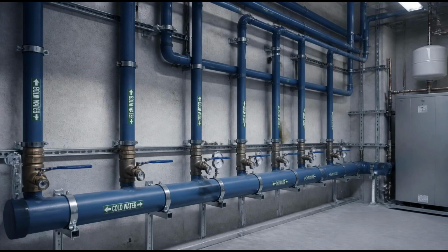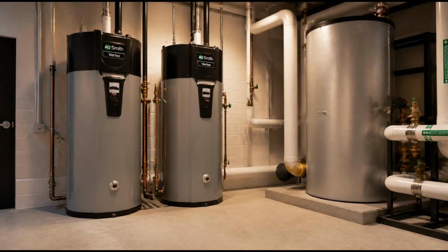Throughout the cold water distribution system, insulation plays a quiet but important role. Cold water pipes passing through warm spaces are subject to condensation, the same process that causes a cold glass to bead with moisture on a humid day. If left uninsulated, that condensation can drip onto building materials, promoting mold growth and gradual water damage. Insulation keeps the pipe surface above the dew point of the surrounding air, preventing condensation from forming.